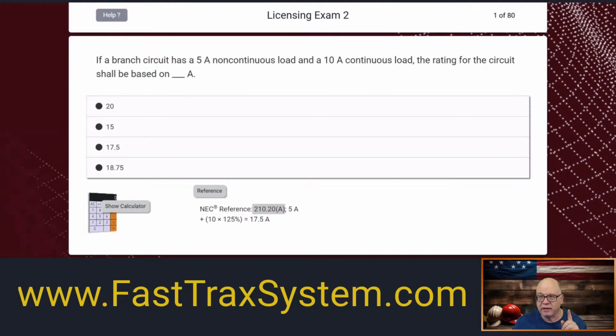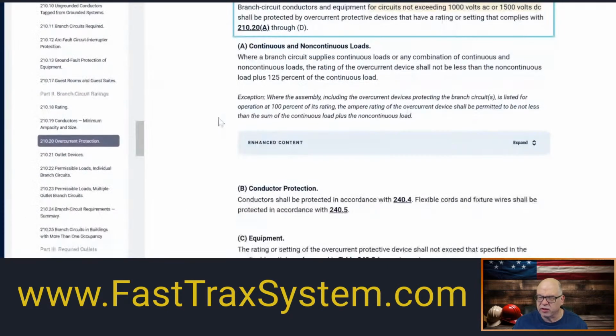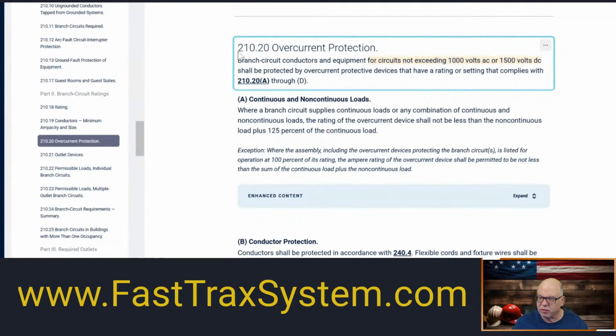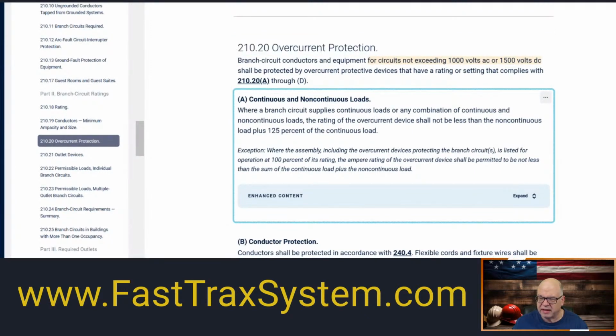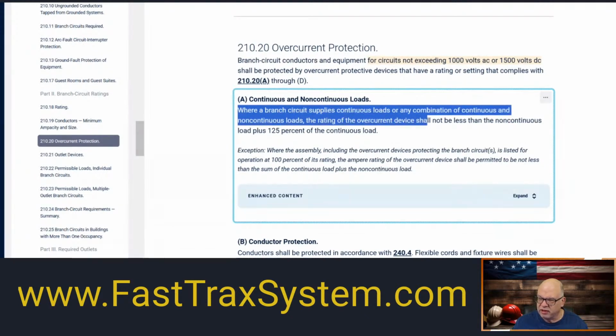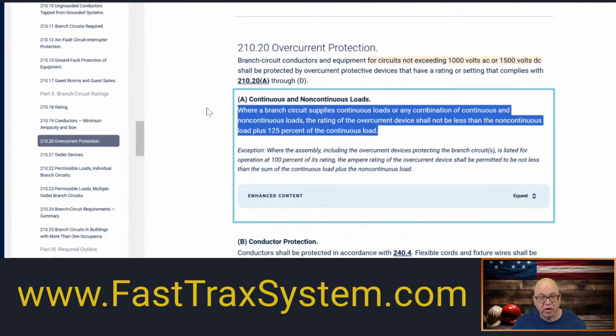Overcurrent protection is 210.20, and it is basically the same thing. Continuous and non-continuous loads. Where the branch circuit supplies continuous loads or any combination of non-continuous and continuous loads, the rating of the overcurrent device shall not be less than the non-continuous load plus 125% of the continuous load. Not less than that. So, still 17.5. It doesn't correspond to a standard overcurrent protective device, then you're allowed to use 240.4(B), and we went up and we're protecting it at a 20 amp overcurrent protective device.